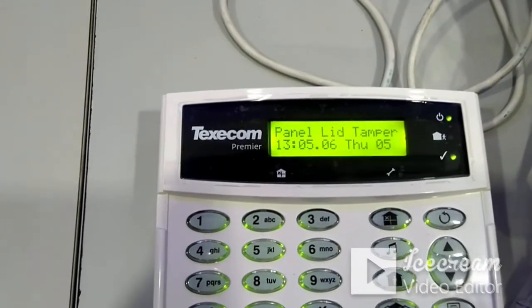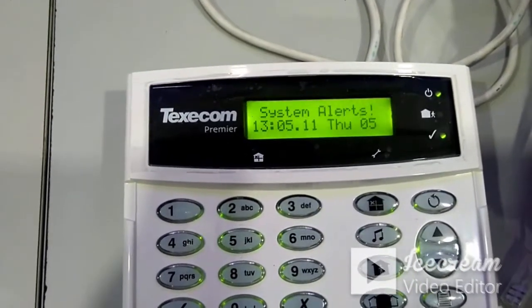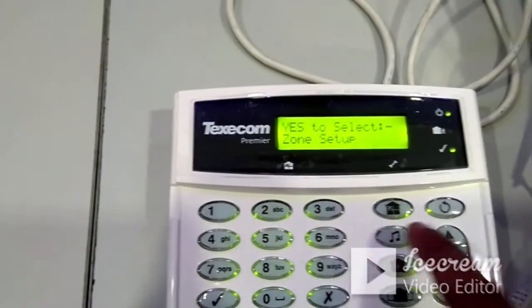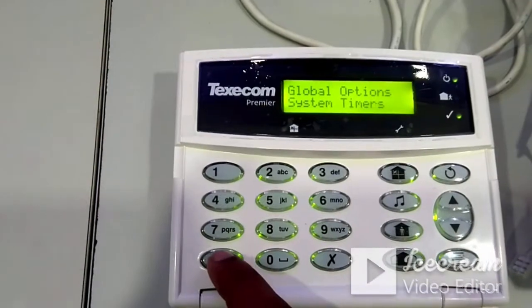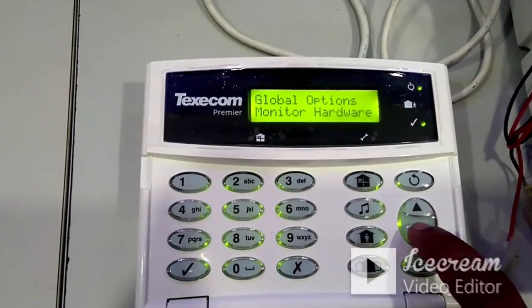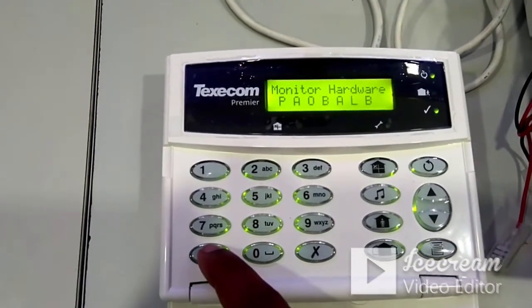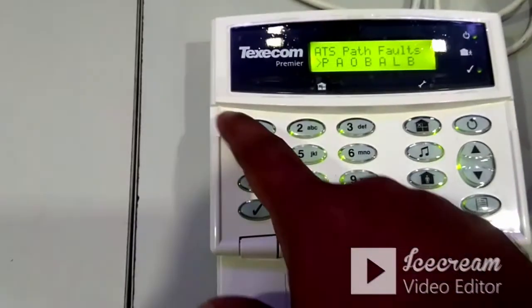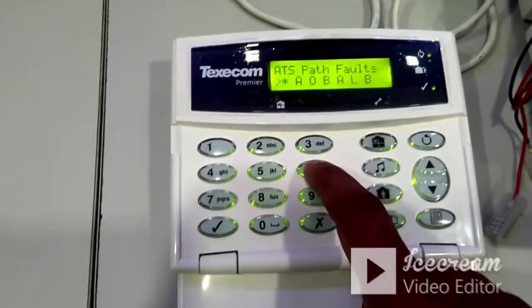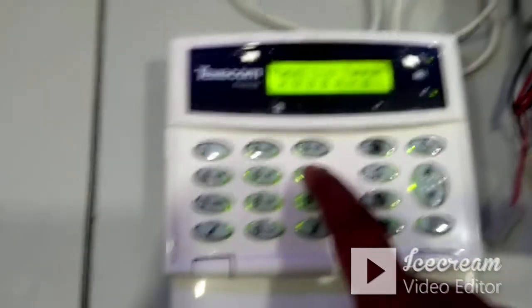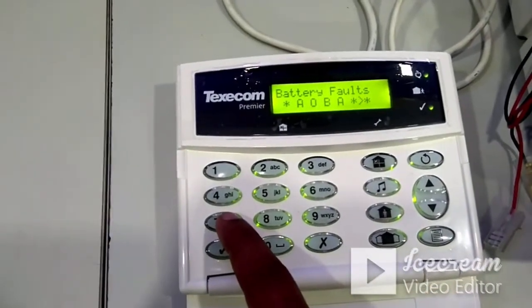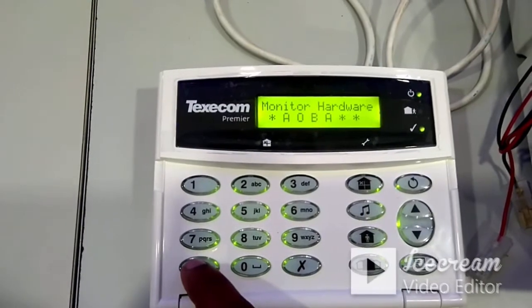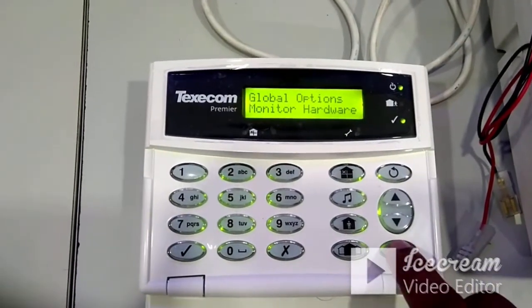To clear faults showing on the panel — such as tamper and battery not connected — if you don't want to monitor these, temporarily bypass them. Press 1-2-3-4, go to zone setup, press the down arrow to global options, then find 'monitor hardware.' Press Yes, then press No to edit. Press 1 and then 6 to disable panel tamper fault monitoring, and press 7 to disable battery monitoring. Press Yes to save the changes.